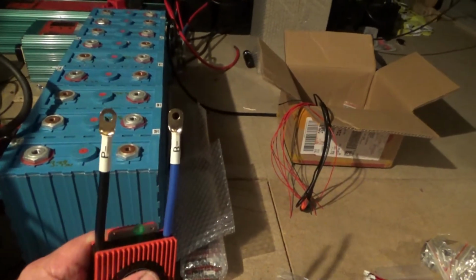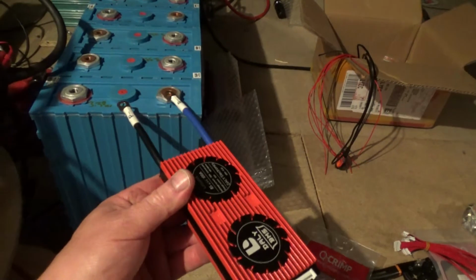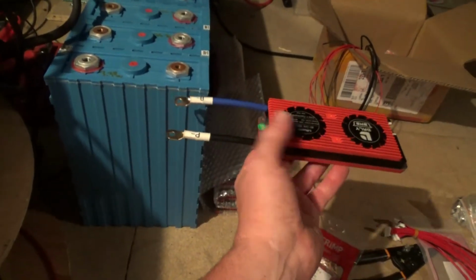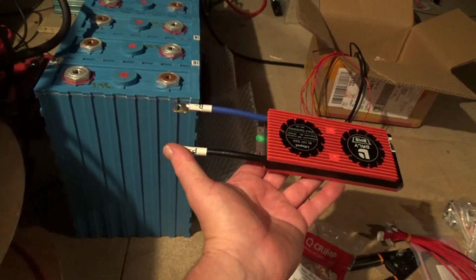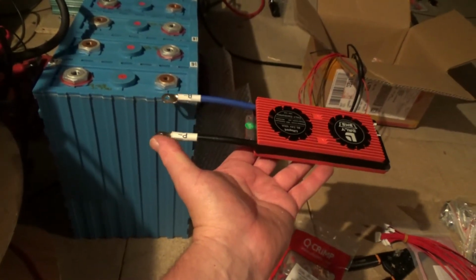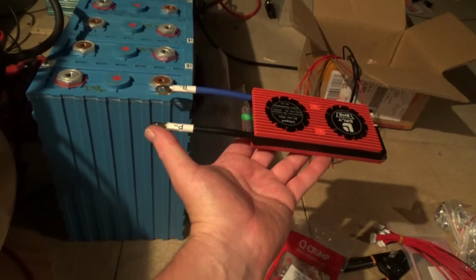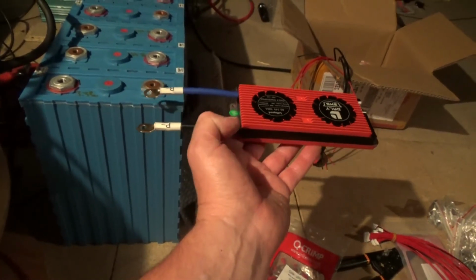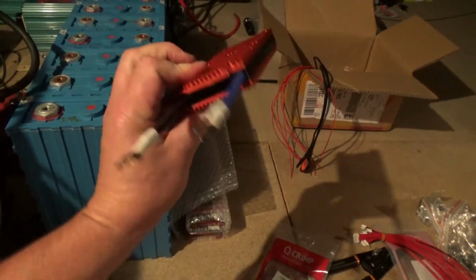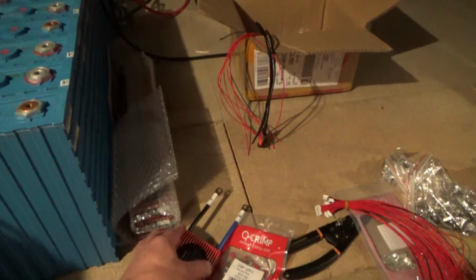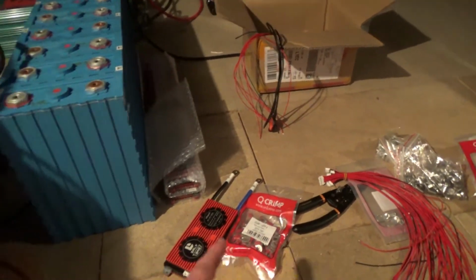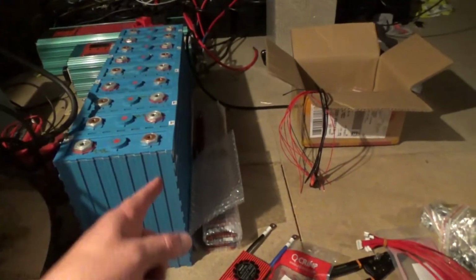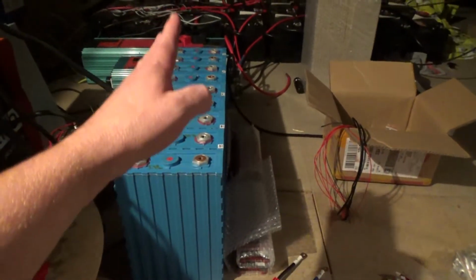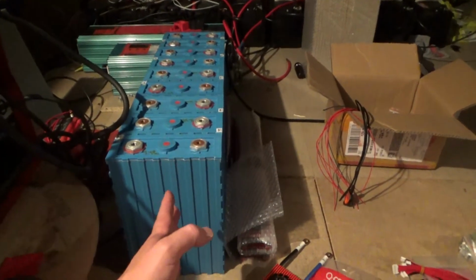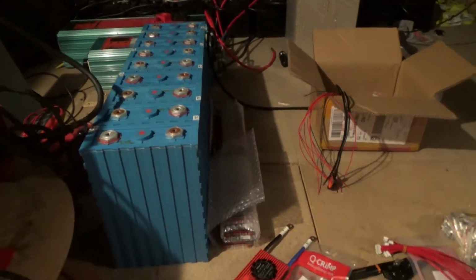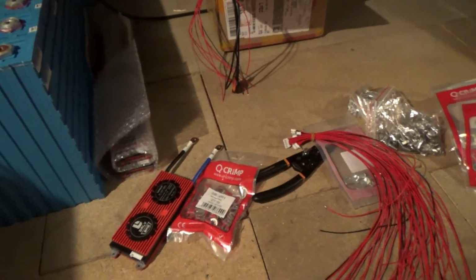We've got power negative and battery negative, so the battery negative will go on there, coming off there like that, and the solar and inverters will be connected to the power. If anything goes wrong, the BMS cuts off and doesn't allow the negative to go through it anymore. It's just like a big switch for 100 amps, slightly intelligent, meaning it can measure the voltage of each battery individually. Any cell goes down, it cuts off. If voltage goes below or above a certain threshold, it cuts off. It's there to protect the battery system - it's a battery management system.